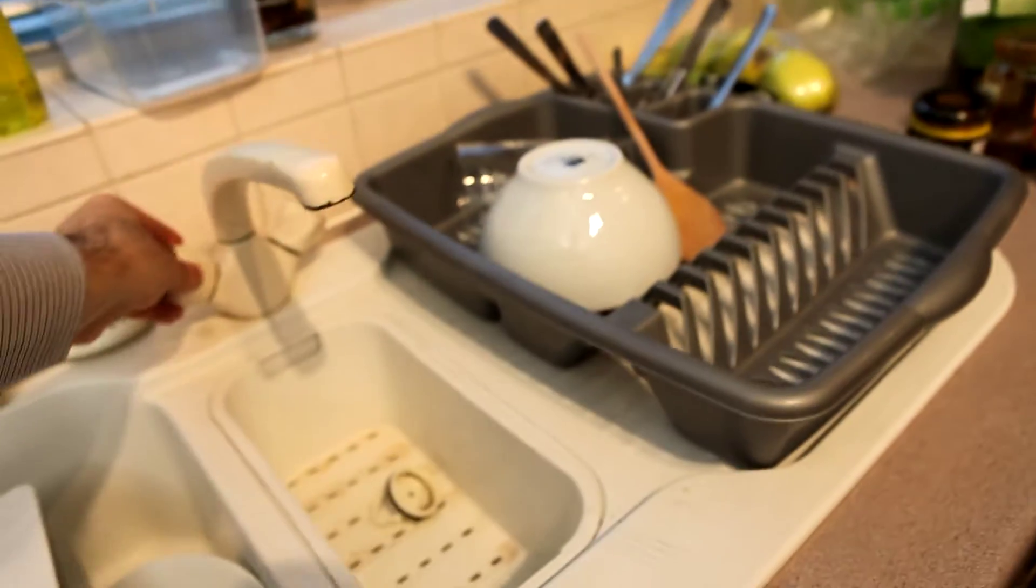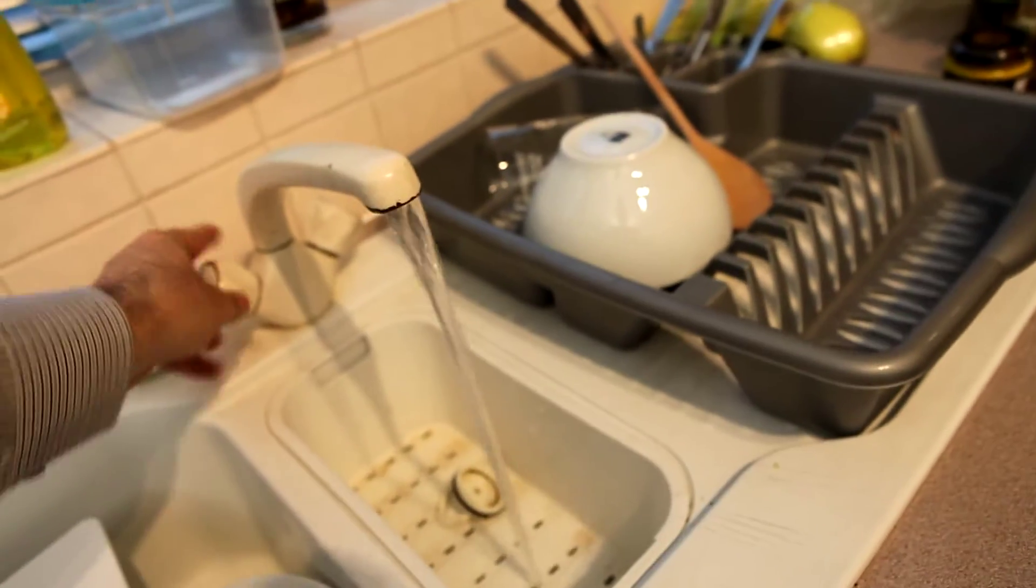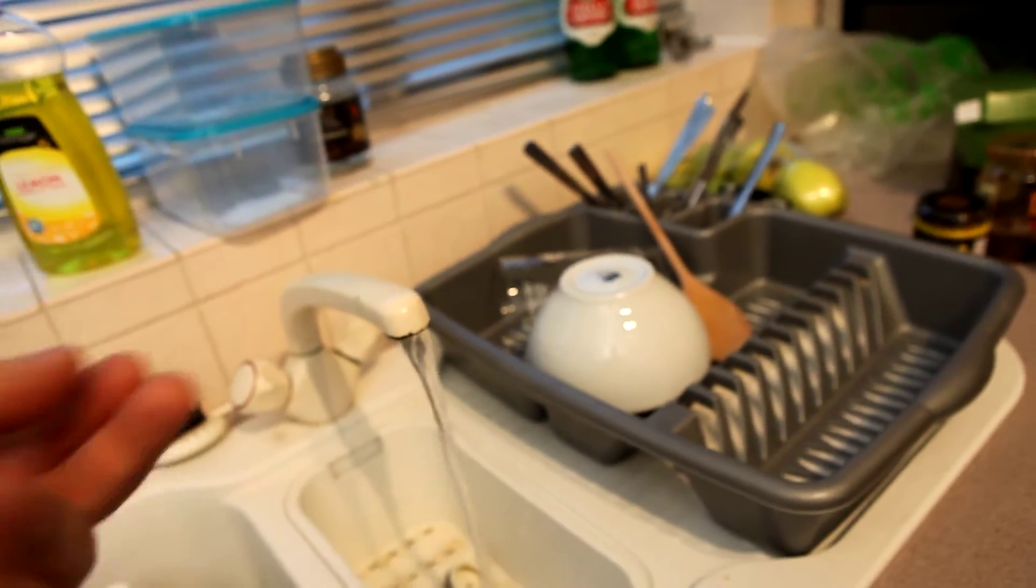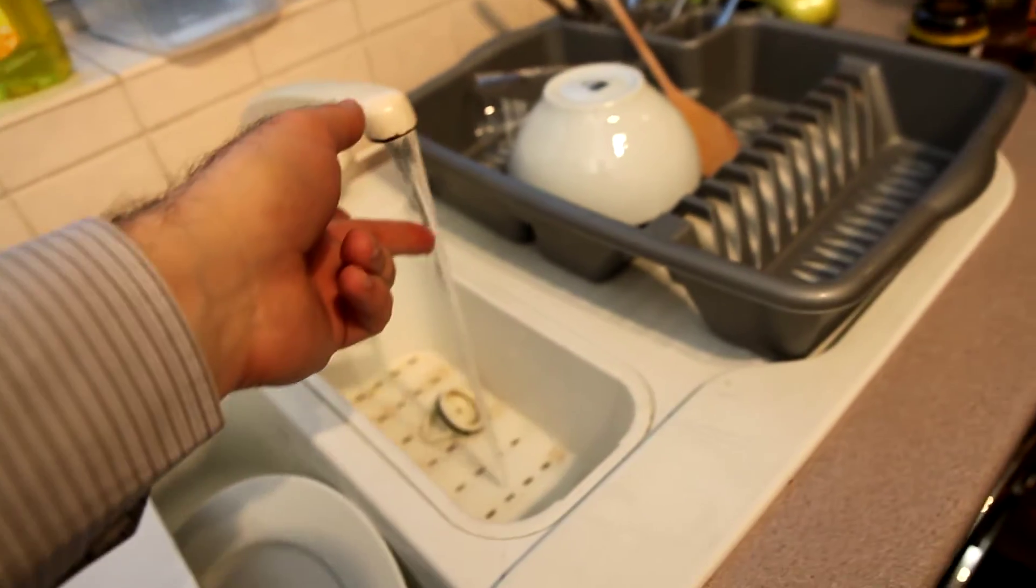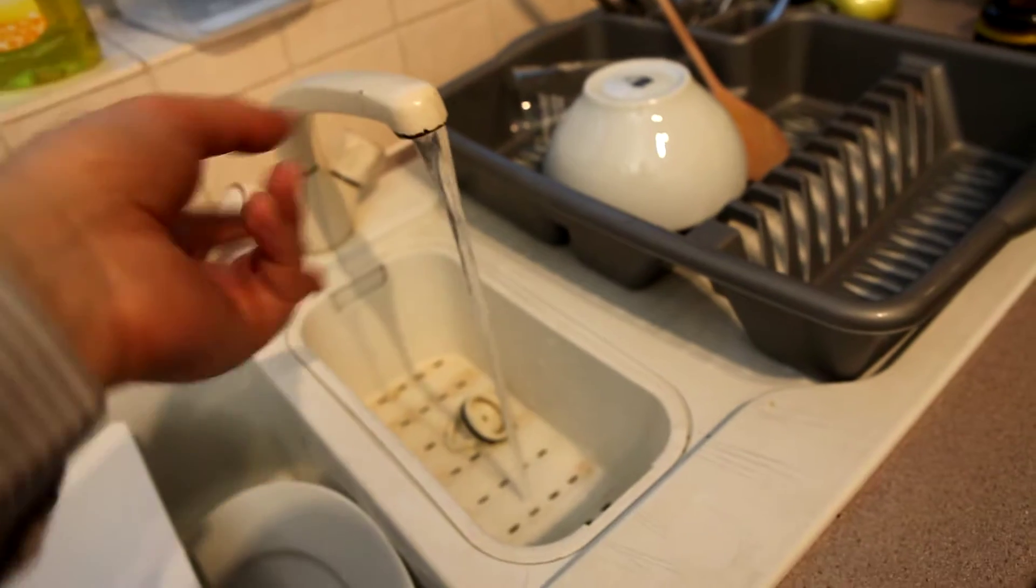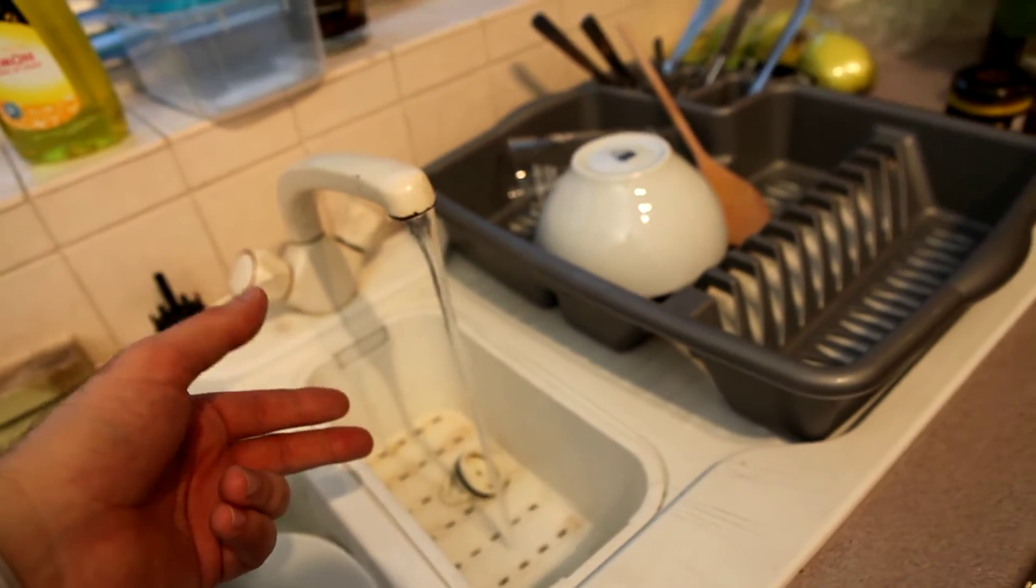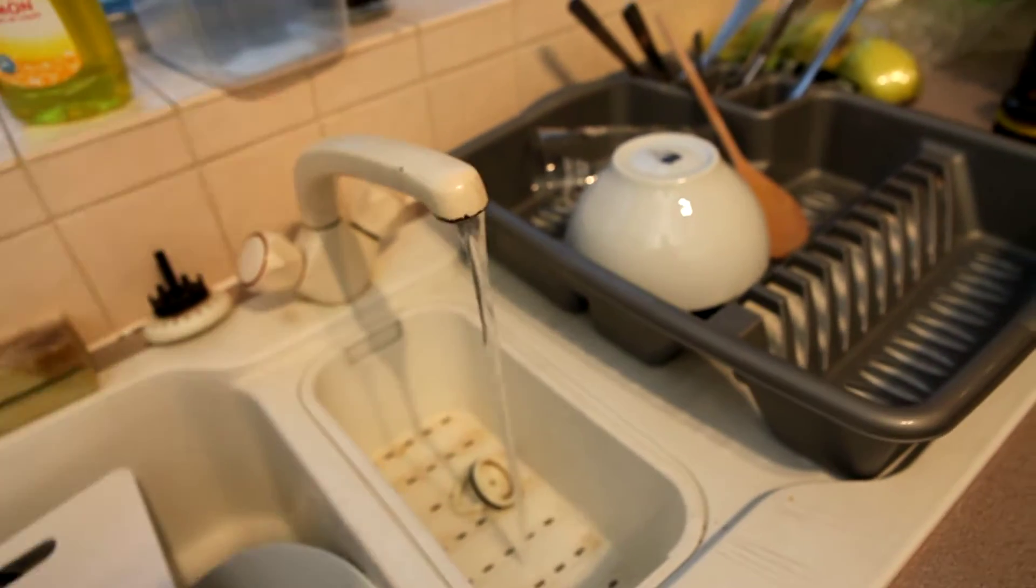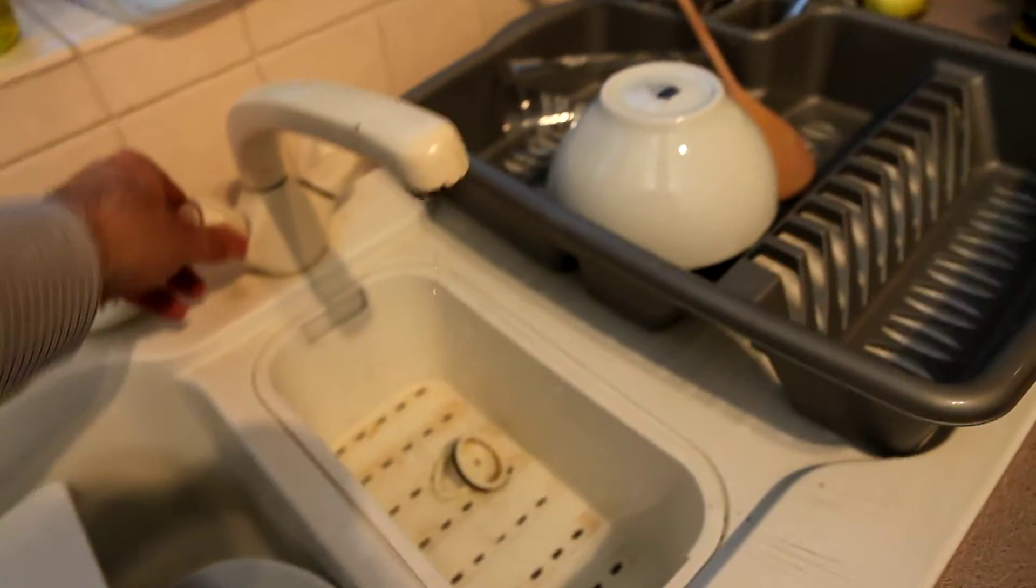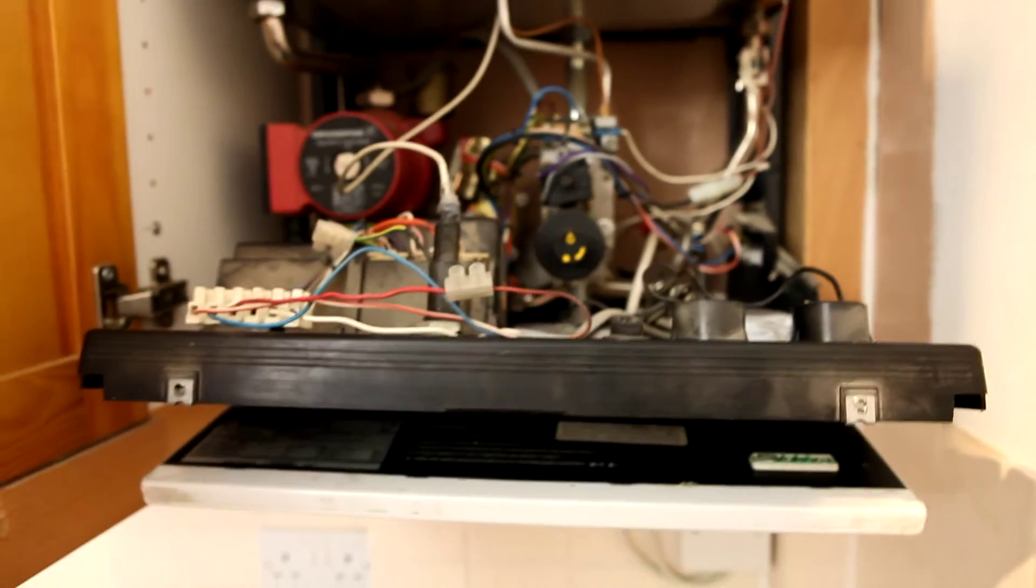The problem with the boiler is that when you turn the hot water on, it's a combination boiler, the hot water comes on, the boiler fires up, you may be able to hear that. The hot water then gets absolutely scalding hot, then the boiler cuts out, flame goes out, water goes ice cold over the next 30 seconds, and then the boiler fires up again, and the water becomes scalding hot, alternates. Complete nightmare, completely useless for showering because even though there's a thermostatic valve on the shower, a thermostat's not going to do a lot when your hot water is alternatively ice cold and boiling hot.